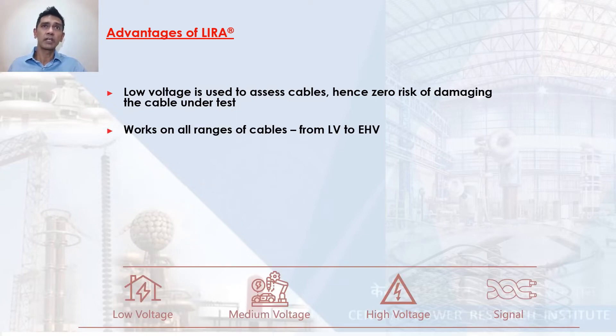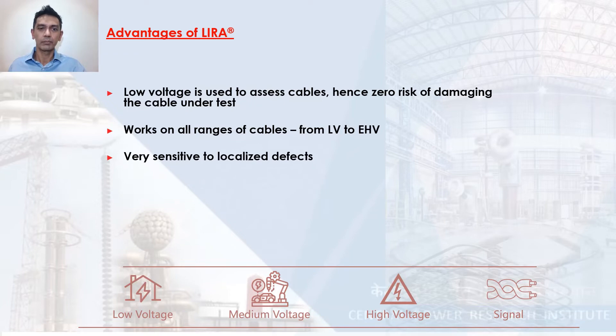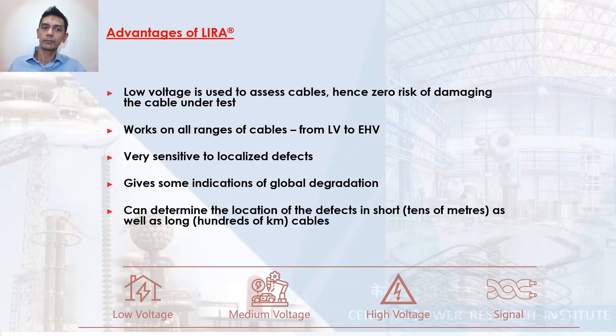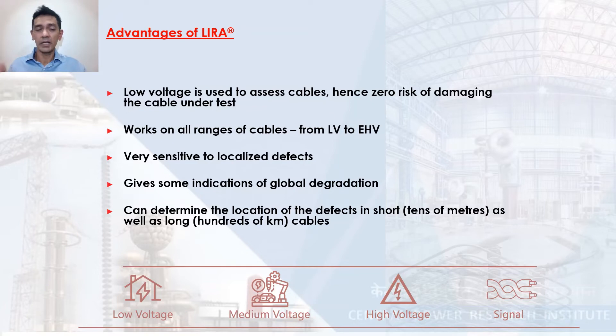It works in all ranges of cables, literally from low voltage cables to extra high voltage cables and even signal cables. It is very sensitive to localized defects in the cable and gives some indications of global degradation also. It works on finding the location of defects in all lengths of cable, from something as short as tens of meters to something as long as hundreds of kilometers.